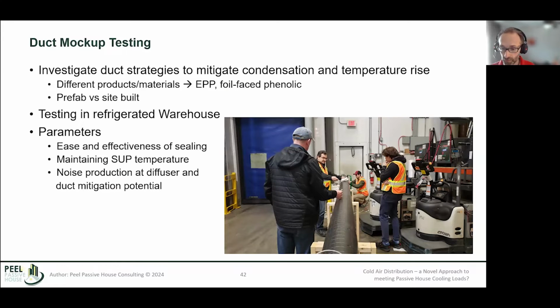One of the first things we're doing, because we've identified duct installation as a key challenge around condensation, is investigating different strategies to mitigate that condensation and the temperature rise from cooling coil to diffuser. We're trying out different products and materials. EPP foam is one of them, which some of you may have come across with HRV casing. There's also prefabricated versus site-built ducts—ready-made ducts from the factory versus site-building ducts from sheets of insulation. I'm really looking at ease of installation and effectiveness of the sealing: can it maintain the desired supply temperature? And where we can, we're going to test out noise production from the diffuser and see if we need to mitigate that.